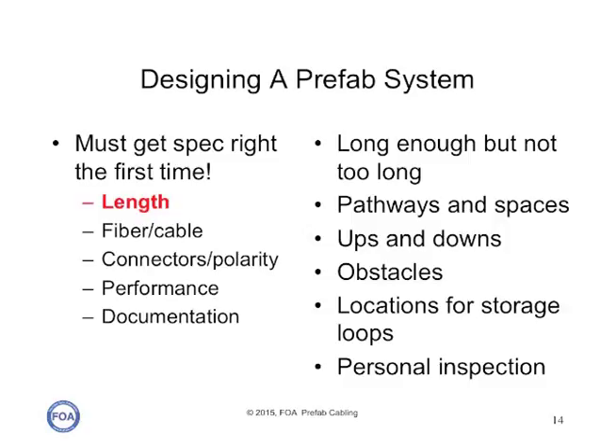So you have to know exactly where the cables will go through all your pathways and spaces. You have to remember where it has to go up and down walls, because that adds a lot of length, and where it has to go around obstacles, because that can add length too. You need to know locations for your storage loops, and you need to do a personal inspection of every square inch of that routing for the cable to make sure you don't miss anything.